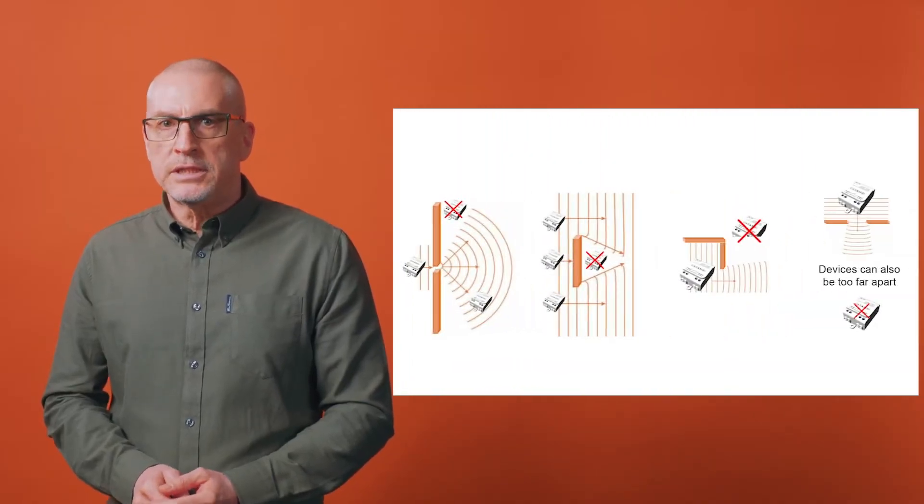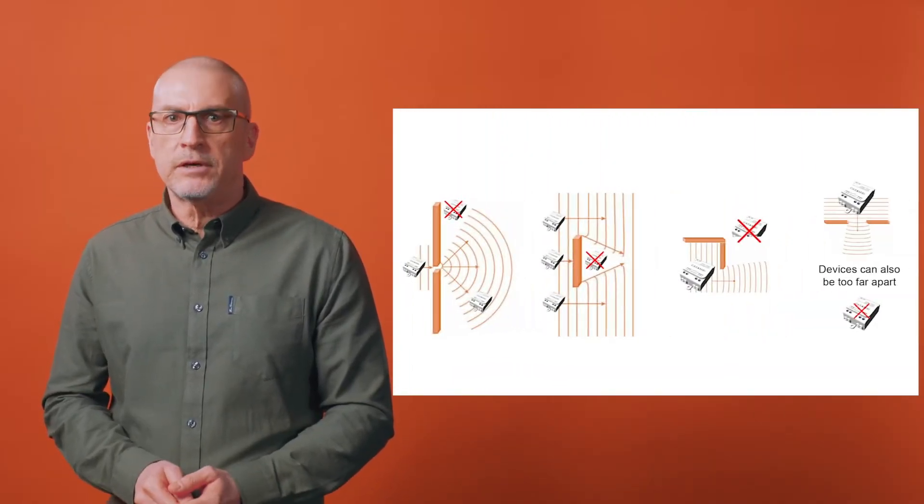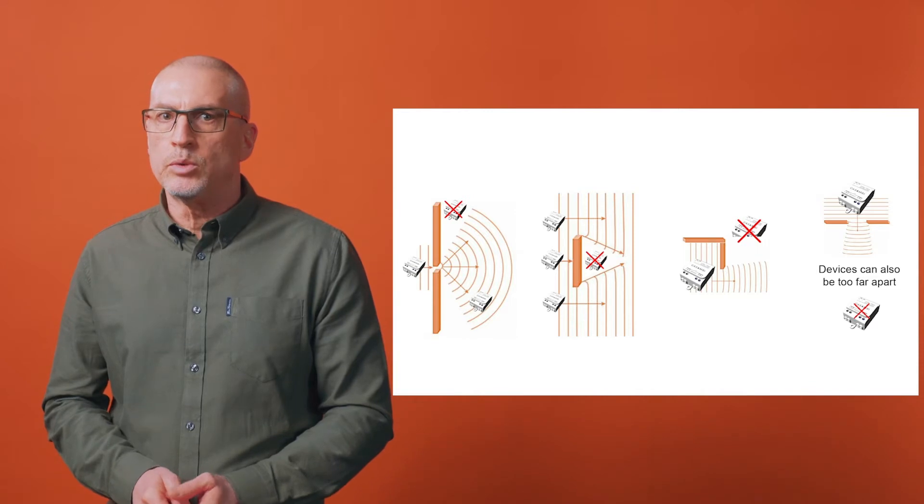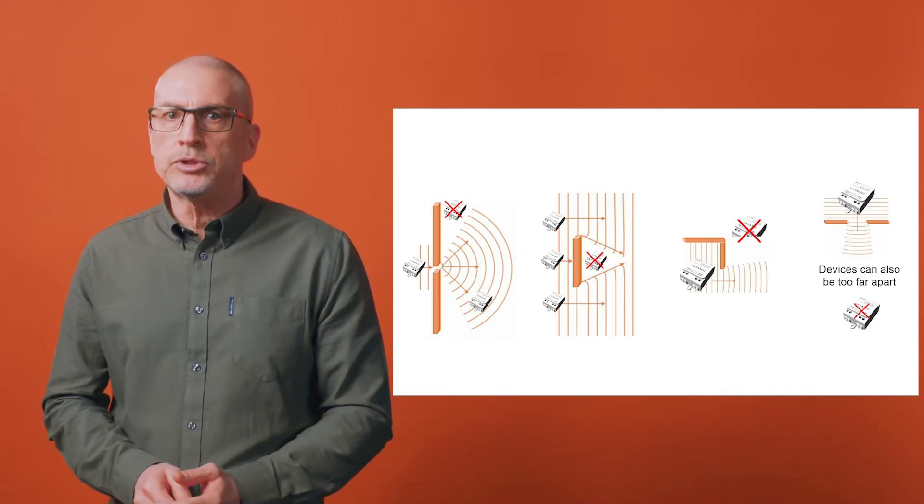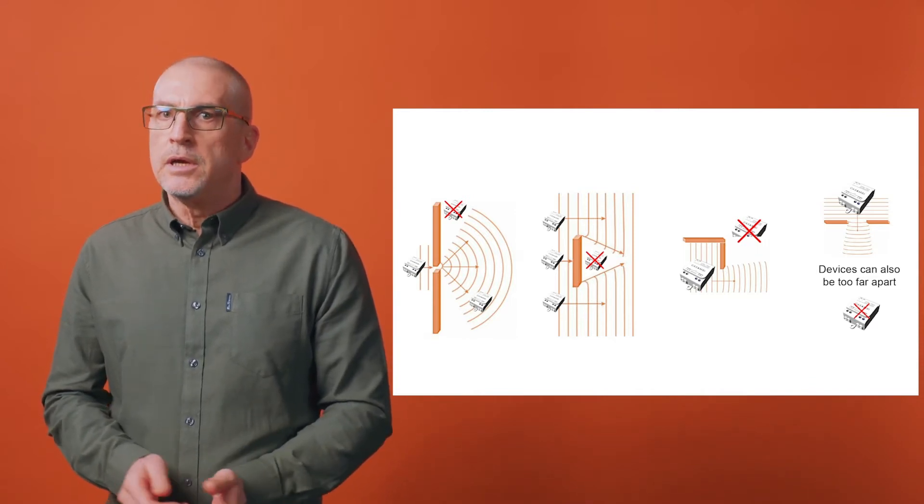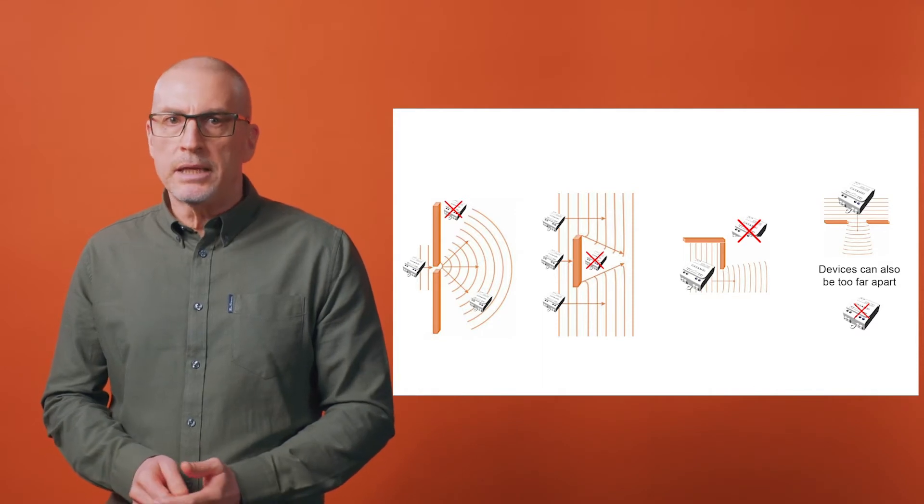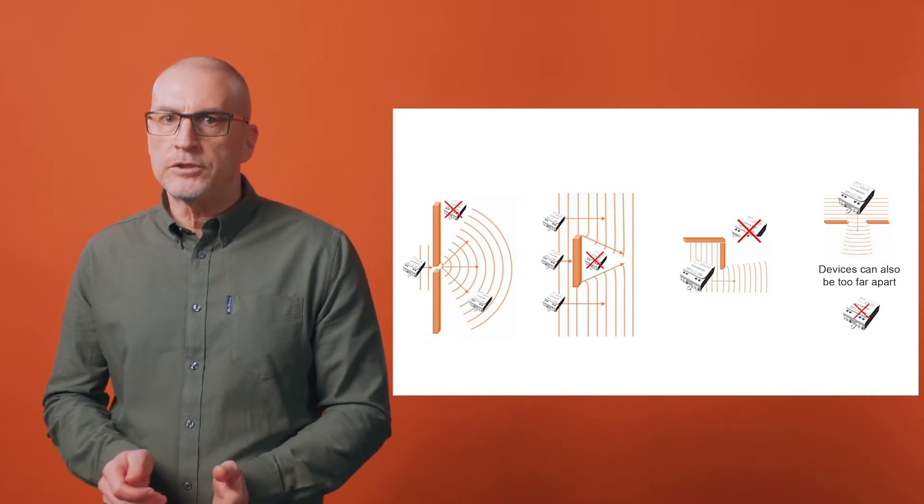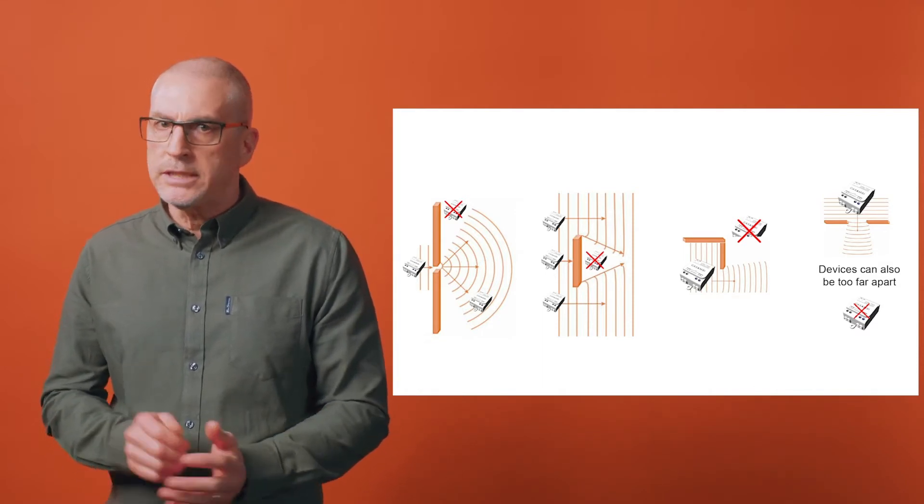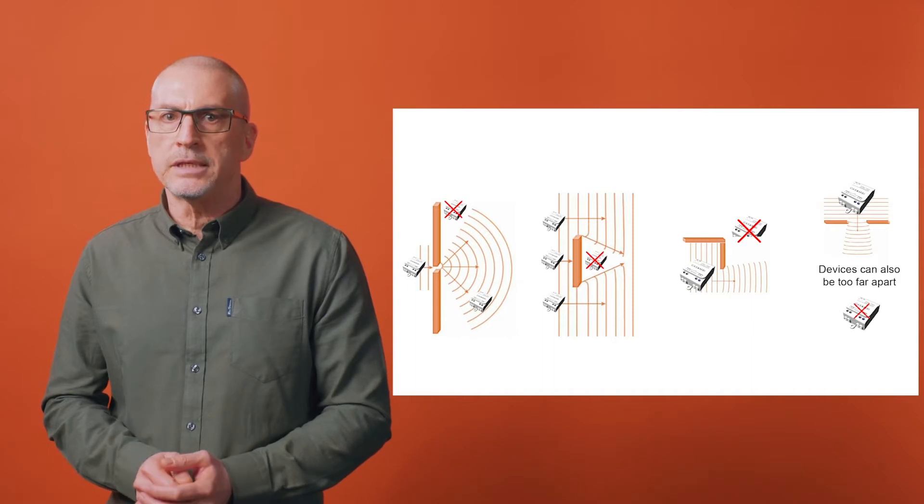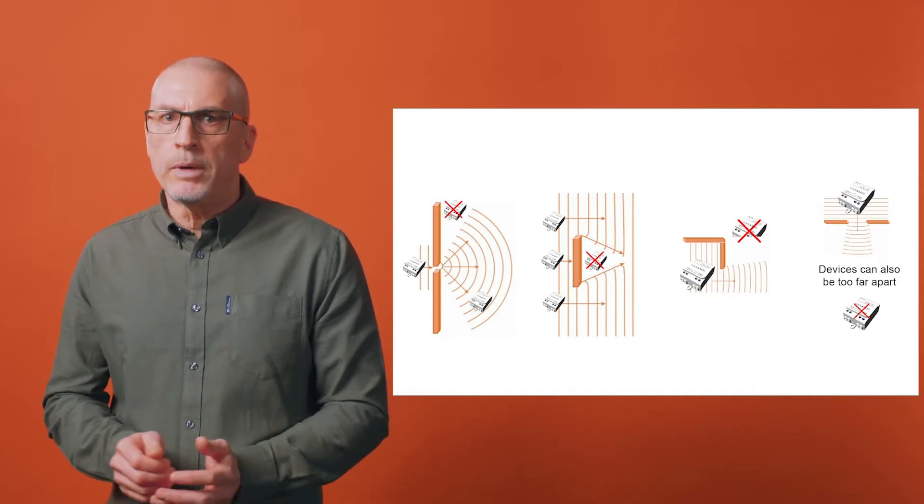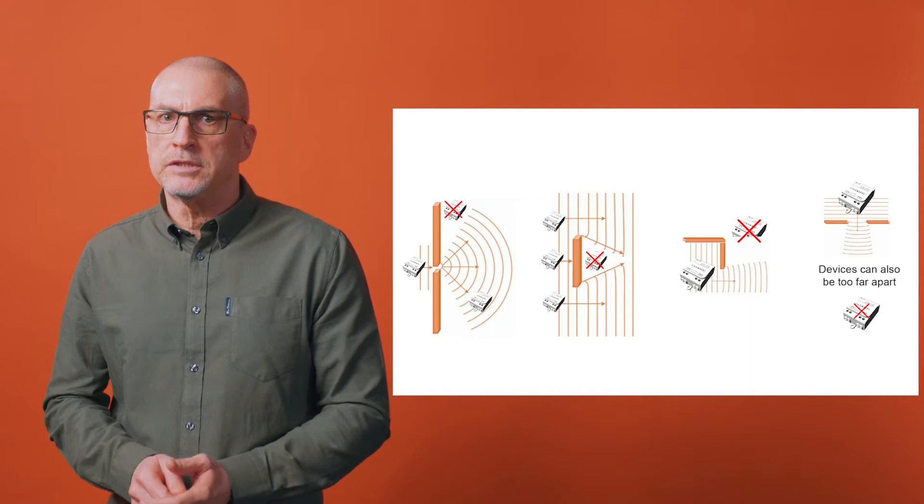Real-life communication distance doesn't depend on the Casambi device itself but on where it's been installed and any obstructions that may reduce or block radio signals. For example, a luminaire with a metal enclosure will have shorter communication distance than an identical luminaire made from plastic, or a thick concrete wall may block the signal between Casambi devices installed in different rooms.